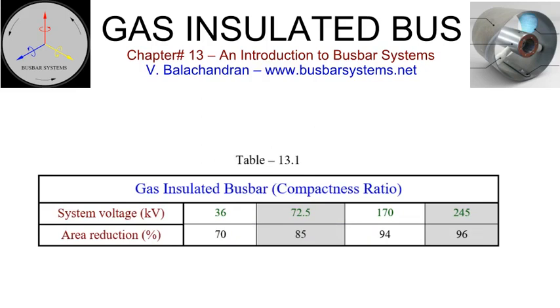Gas-insulated bus can be installed in a horizontal or vertical configuration and run overhead or underground, in trenches or tunnels, or directly buried. These are not expected to be opened, inspected, and maintained for the life of the equipment. Gas-insulated bus is not inflammable and is not a fire hazard. Gas-insulated bus also have a very high electromagnetic compatibility, EMC. The magnetic field, measured as flux density in microtesla, under similar measurements, is significantly lower than that of a cable or an overhead line operating at the same voltage and current. The corona loss in a gas-insulated bus is lower than that of a cable or overhead line for a similar application. A very high degree of reliability is expected of gas-insulated buses.